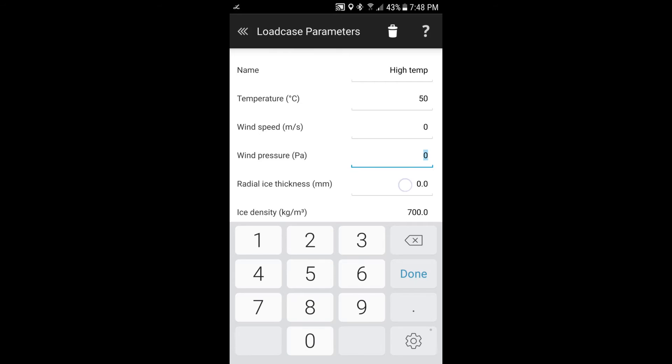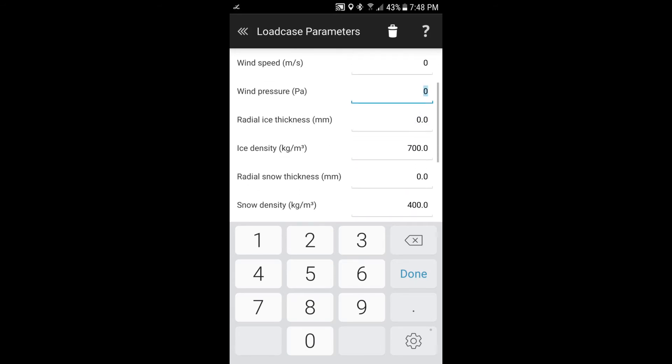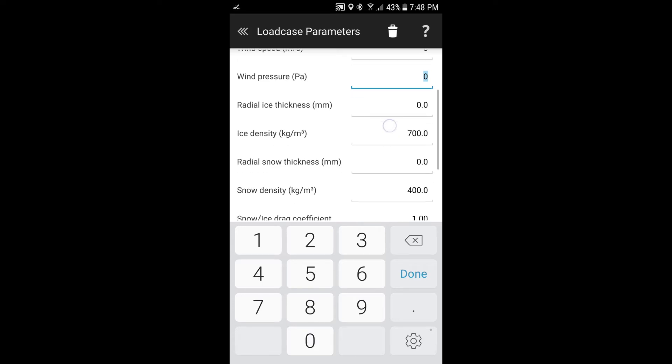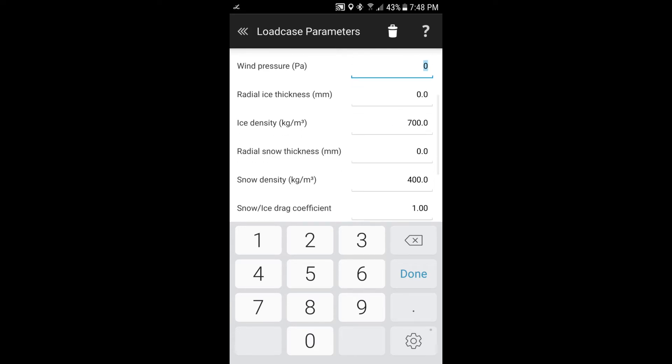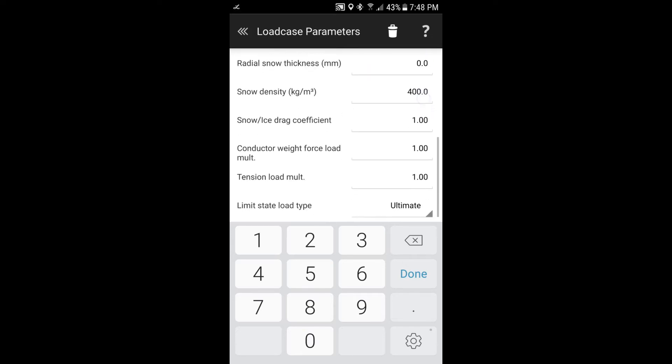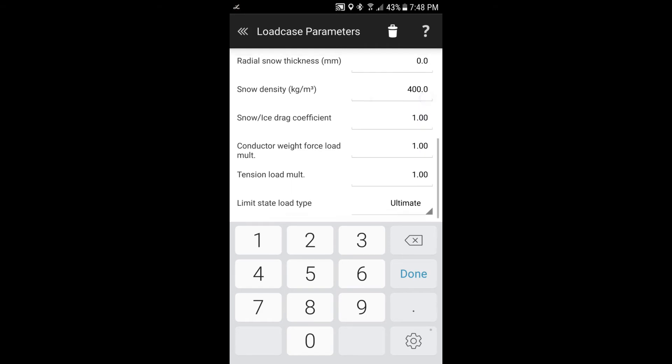The other thing we can add here is radial ice thickness. It's been pre-populated with an ice density, but that can be modified if you'd like. There's also snow thickness that you can put in. And then you can have a drag coefficient that relates to having that ice or snow. We've got other parameters here. Having a multiplier for the weight force and also for the tension. Sometimes when you're creating your load, some standards will require that you have a tension multiplier.